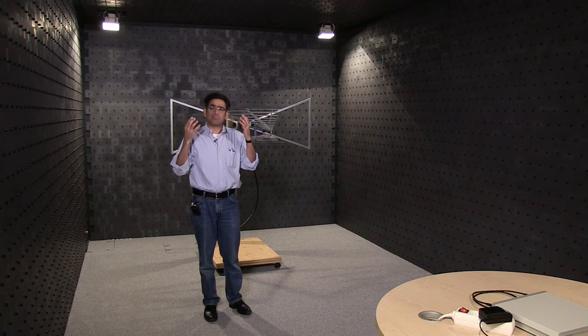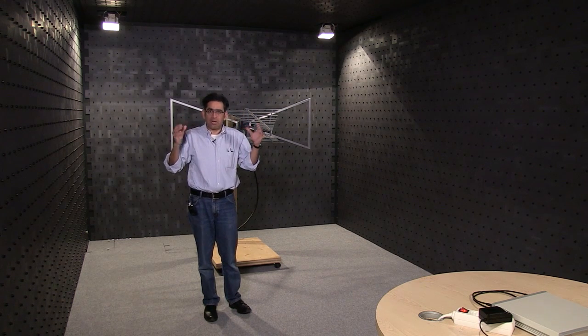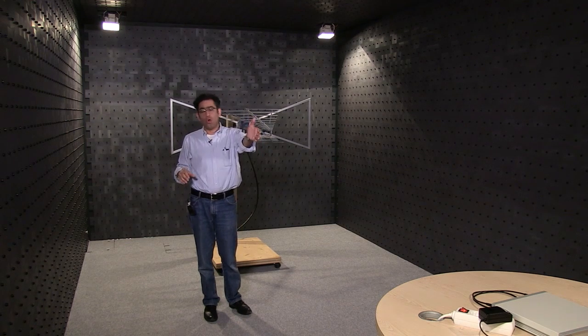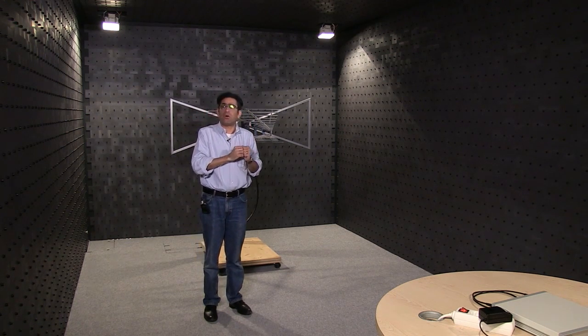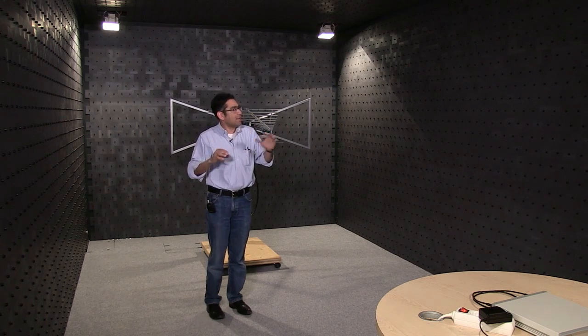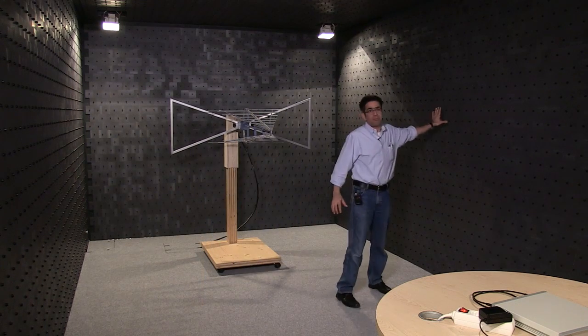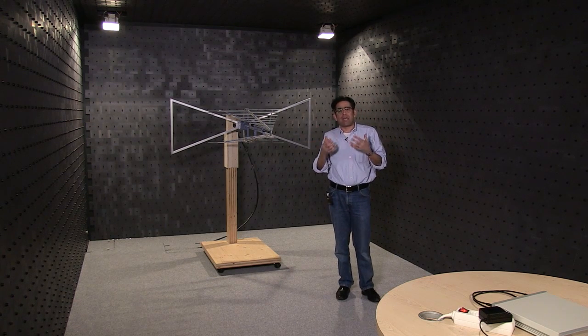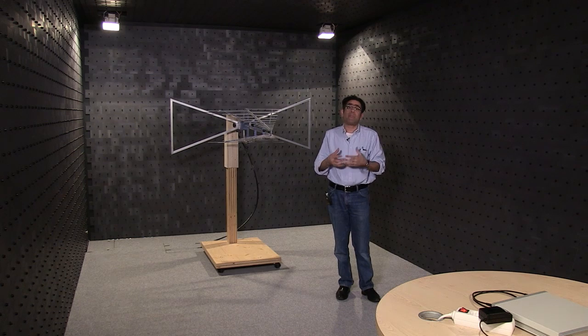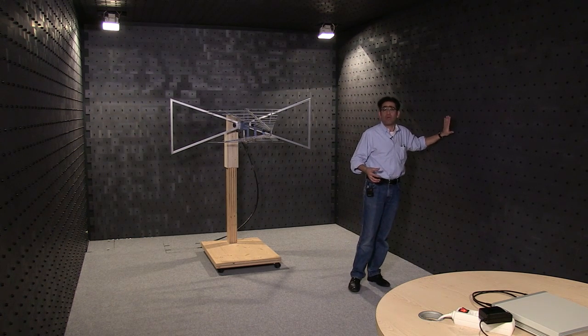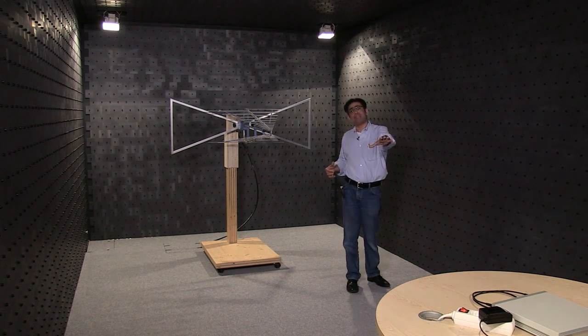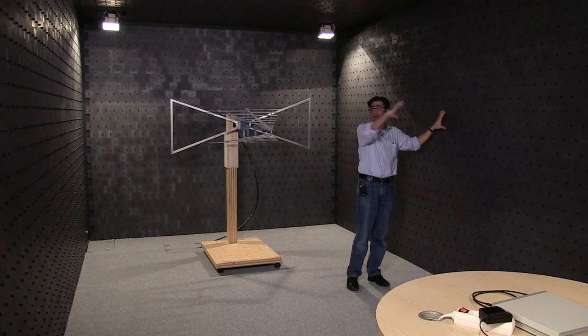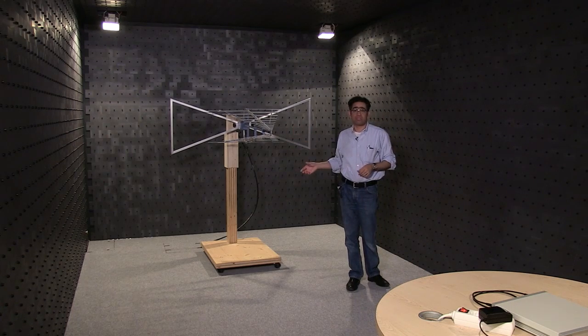The other problem however is that if the metal box is reflecting all of these RF signals, your own equipment on test inside of the metal box is going to emit and reflect off the walls and get picked up by the antenna. So this test is done in an anechoic or semi-anechoic chamber and by that what we mean is that you've got absorbing material on the wall so that whatever is being emitted from your device under test gets absorbed and doesn't bounce back and get picked up by the antenna and corrupt your signal.